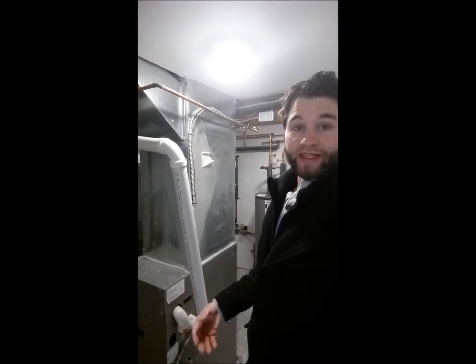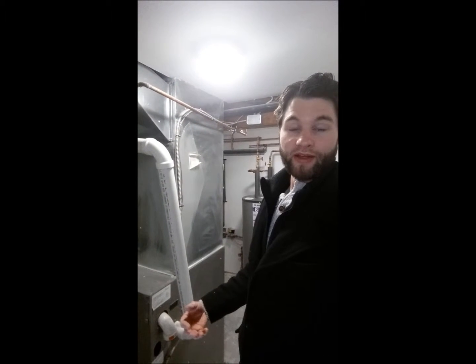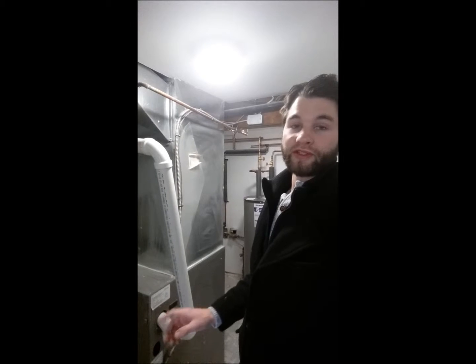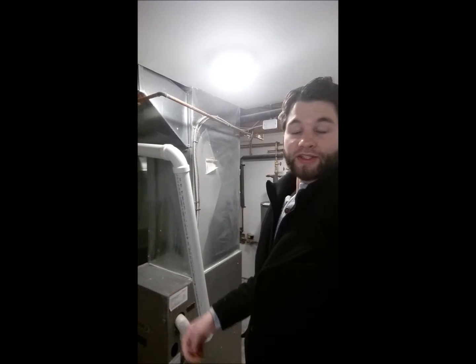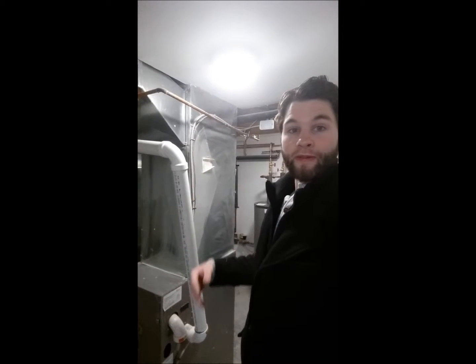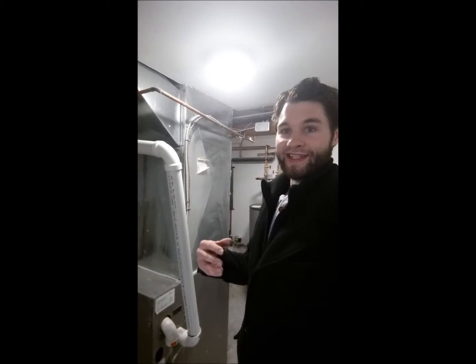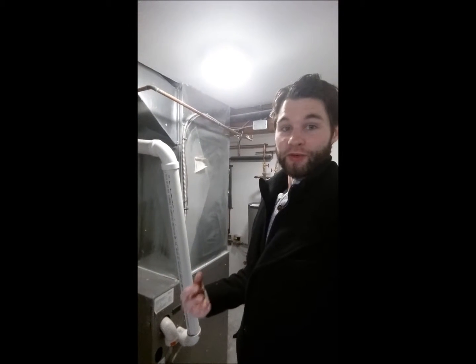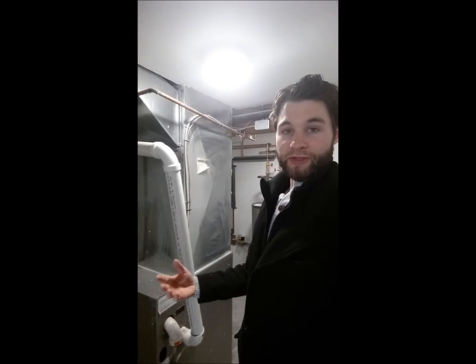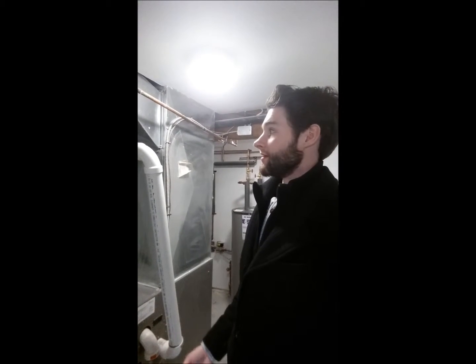A sprinkler system is actually really easy to put in. You're not allowed to put it in with PEX tubing, which is very important to remember. However, a sprinkler head is actually only about $5. So for anybody looking to do a basement apartment and put a sprinkler system in, it sounds like a big scary thing, but it's really not. For about $5 per sprinkler head, maybe 10 depending on where you buy it, and about 40 to 50 bucks in copper and fittings, you can have a sprinkler system that's fire compliant and ready for the bylaw to inspect.